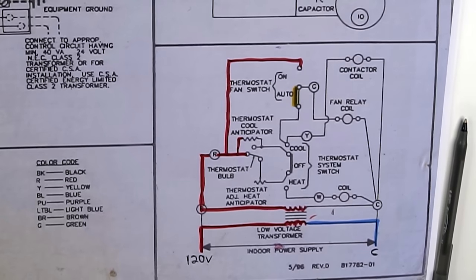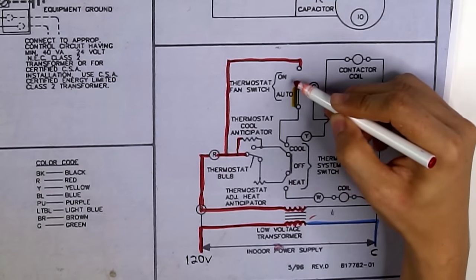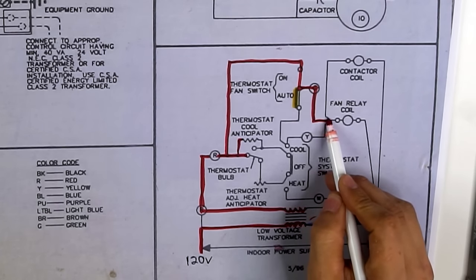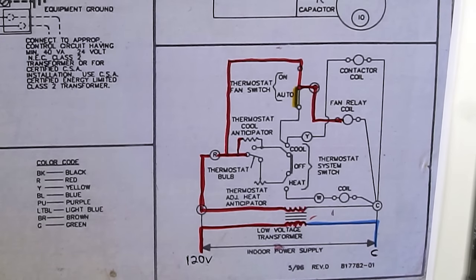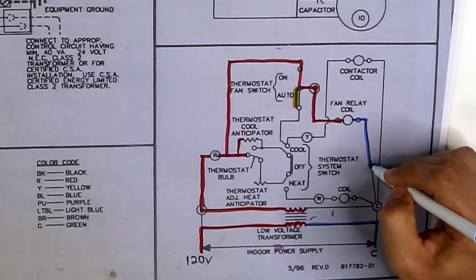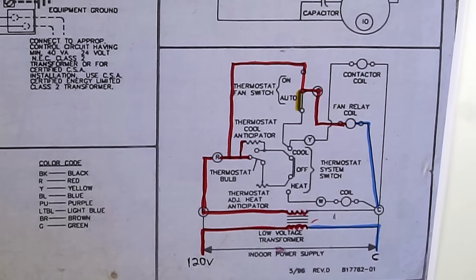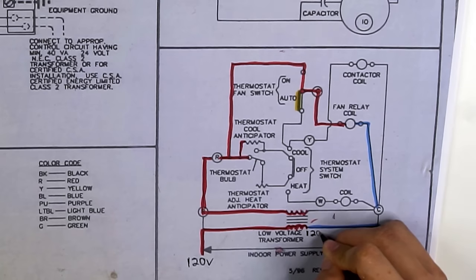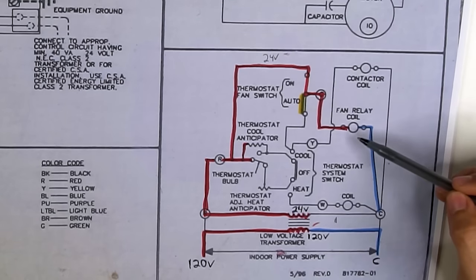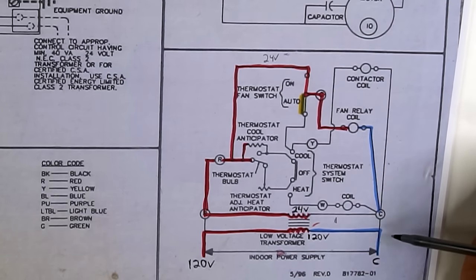If you move the fan switch on the thermostat from auto to on, this bar will close and send power through the G line, which goes into the fan relay coil. Once the fan relay coil energizes, that will turn on the blower fan inside your furnace. The transformer is getting 120 volts and putting out 24 volts. So everything after the transformer is 24 volts. Turning the fan switch to on closed this circuit and energized the fan relay coil, which powered the blower motor.